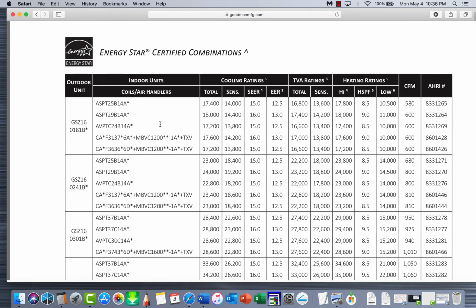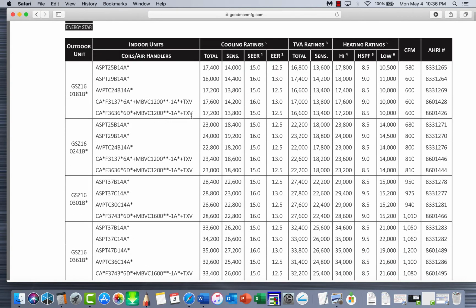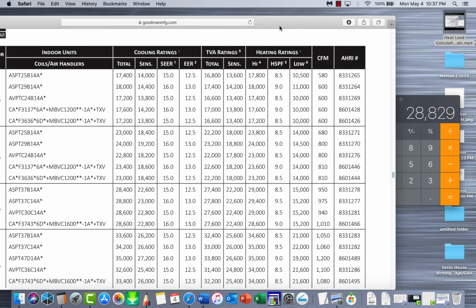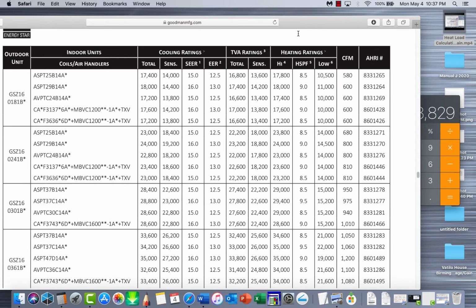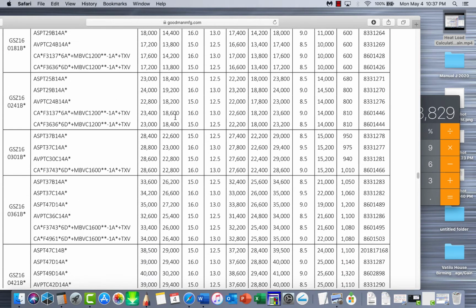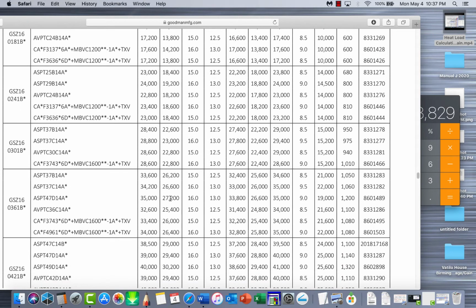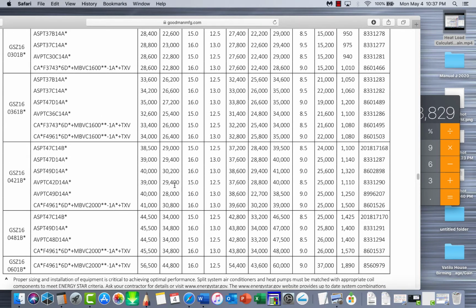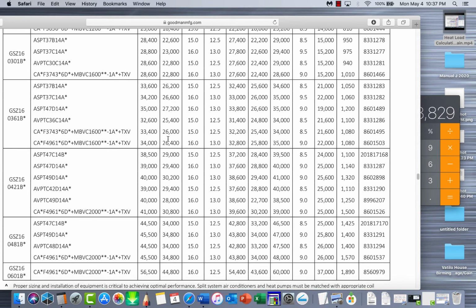What we're wanting to look at is this right here, the sensible. Now basically that's what we measured right there, was 28,828. So we want to meet that. Now remember, this is for 99%, 1% of the time. So we want to make sure we're making this number right here. So when you start scrolling down through here, we want to get one that's closest to it.